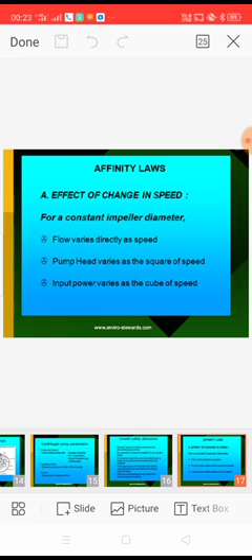Effect of change in speed: for a constant impeller diameter, flow varies directly as the speed. Pump head varies as the square of speed, and input power varies as the cube of speed. Change in size: for a given casing with different impellers, flow varies directly as the impeller diameter, pump head varies as the square of the impeller diameter, and input power varies as the cube of the impeller diameter.